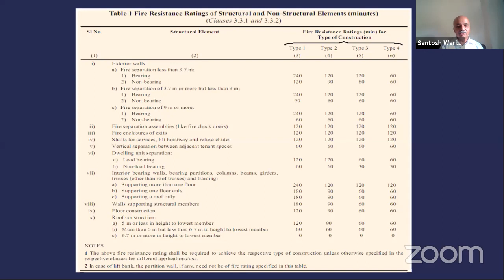And here they have specified the external walls, then internal walls, the fire enclosures, then internal barriers, then the walls and roofs of the type 1 and type 2 construction, wherein as far as compartmentation is concerned, the minimum requirement specified is 120 minutes, or 2 hours. For the details of Table 1, there is another annexure, Annexure C, attached to Part 4, wherein different materials and their fire resistance are given in different tables. There are almost 8 to 9 tables in Annexure C of Part 4.